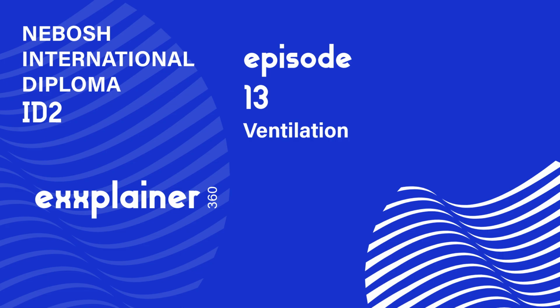You need maybe 20 meters per second transport velocity for heavy dusts, like from grinding. For serious stuff. Okay, after the ducts, the air goes to the air cleaner. The filter. Right. And what you use depends entirely on what you're catching. Is it solid particles, or is it gases and vapors? Let's do solids first. Particulates.